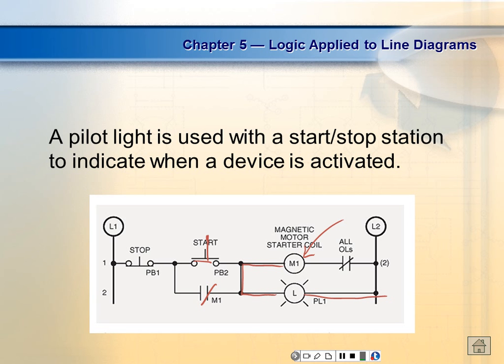What? The contact just won't work. Yeah, so I was looking at it from a normal operation point of view, and y'all was looking at it from a problem point of view, so we wasn't on the same wavelength. So what they're saying, if the coil is bad, or what we're saying now, we're speaking with one voice, right? So if the coil is bad and the light is good, you press the start button.